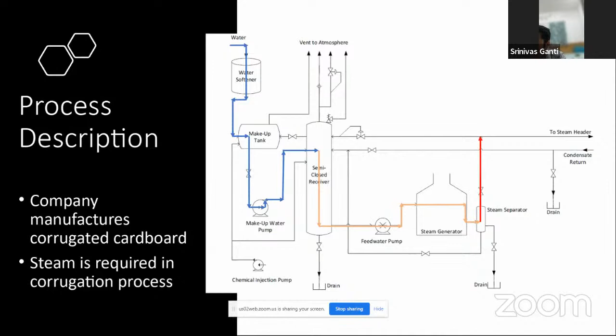During the corrugation, steam will lose its latent heat and become condensate, which will come back to the semi-closed receiver. This semi-closed receiver is like the deaerator in the major utility areas of our process plants. In this, it serves two purposes. Because of the heat from the steam as well as the condensate, whatever dissolved oxygen cannot be treated by the chemicals can be heated up and it will go to the vent.